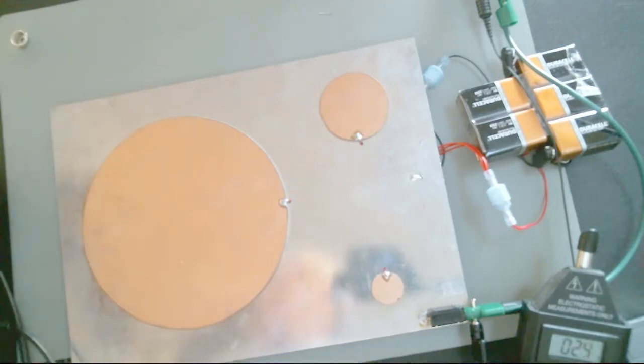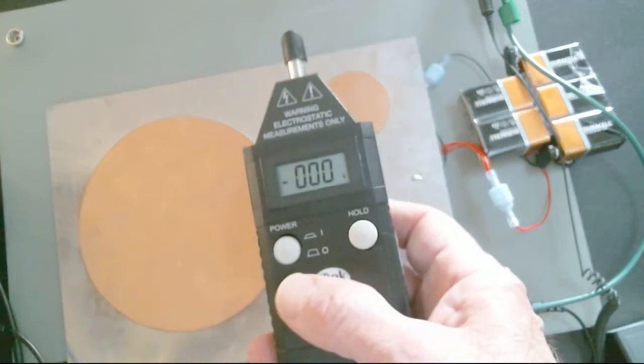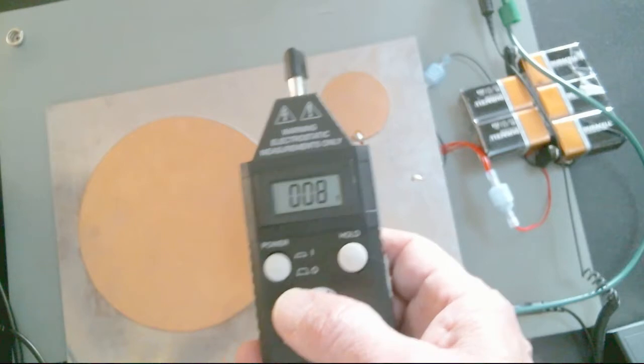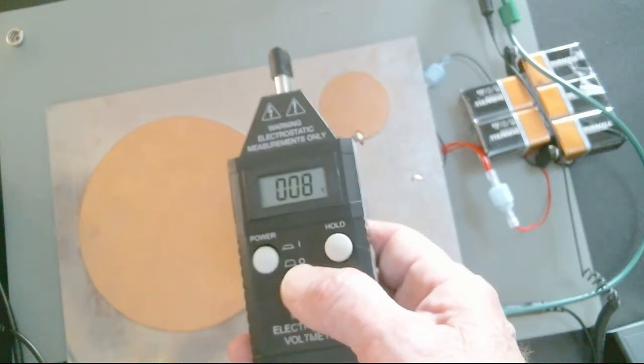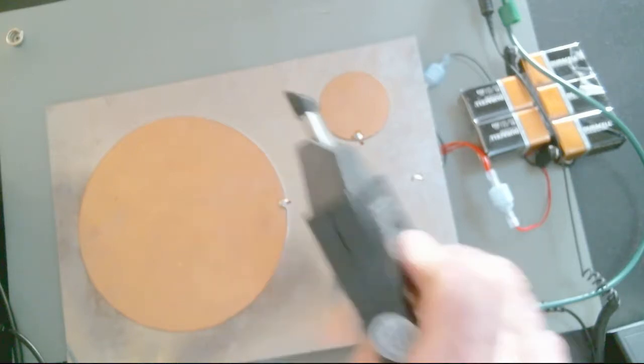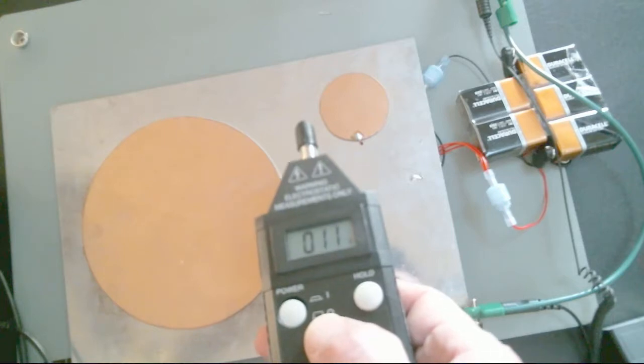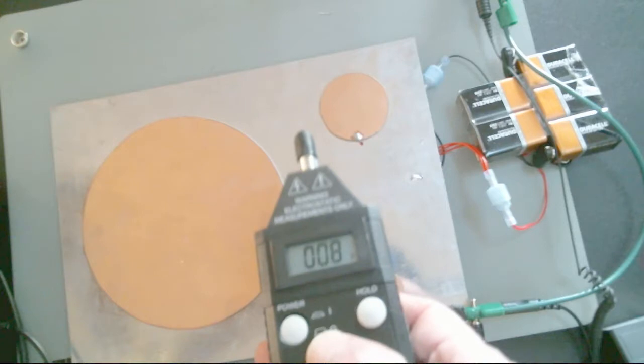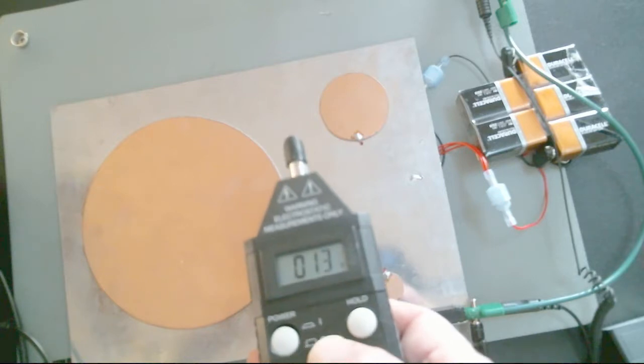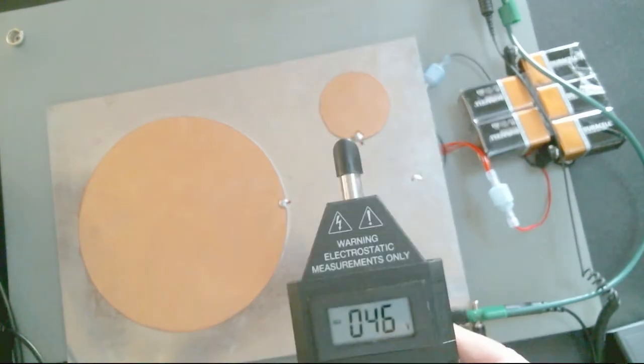Next, we're going to make the same measurements, this time with an electrostatic voltmeter. This particular model has a 2000 volt maximum range. And along with that comes a measurement distance of only a few millimeters, which means you place the probe close to the item that you're measuring. And then you can capture the reading effectively. You'll find that this meter also is less susceptible to distance variation than a field meter. So let's begin and see what we get on the large disk. And you'll see that we ended up with the same reading.